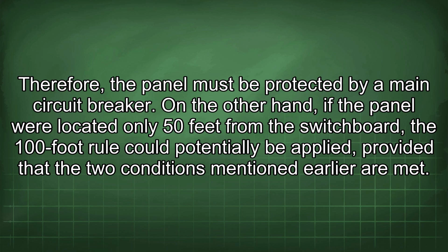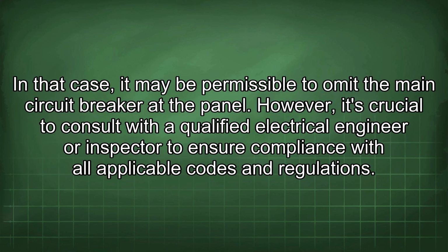On the other hand, if the panel were located only 50 feet from the switchboard, the 100-foot rule could potentially be applied, provided that the two conditions mentioned earlier are met. In that case, it may be permissible to omit the main circuit breaker at the panel.